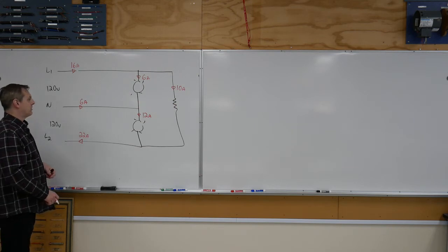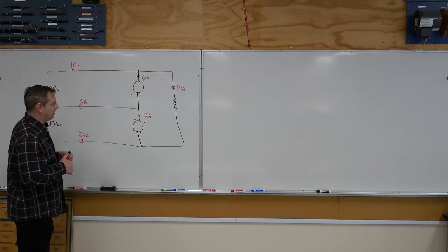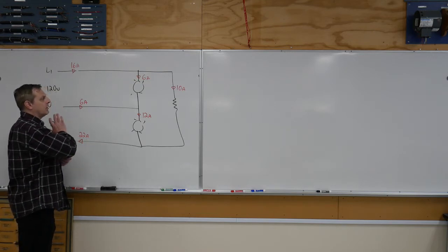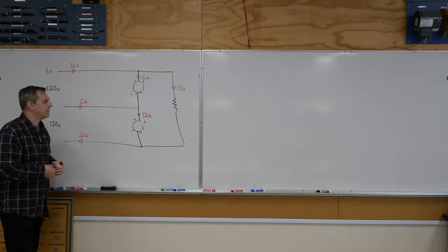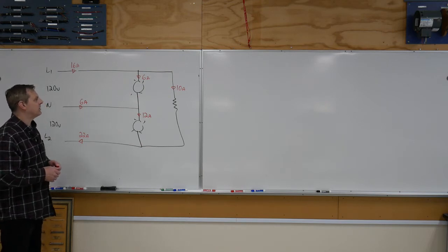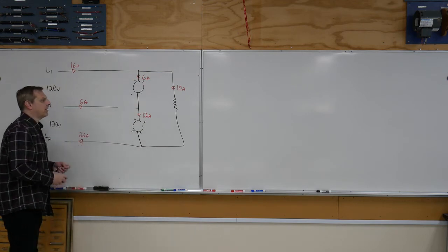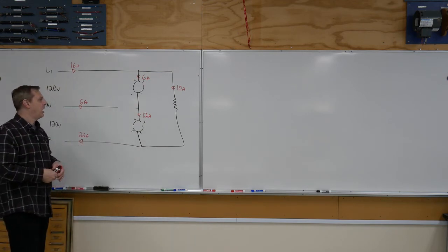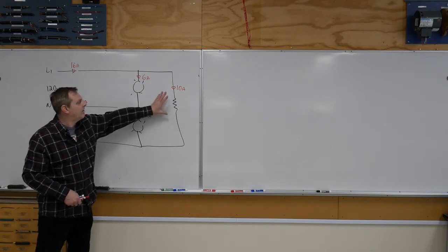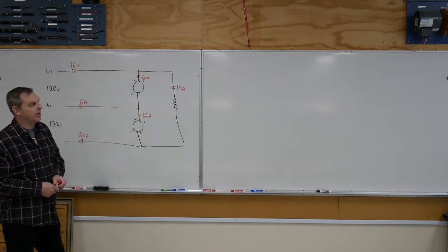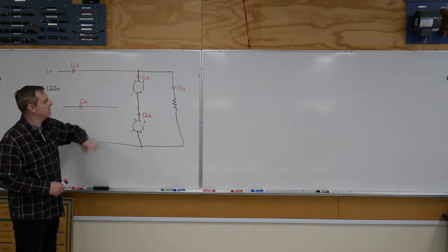So in this circumstance, with the unbalanced neutral, if all our connections were good, this is the worst case scenario, or I guess the best case scenario you could say. However, if we made a mistake and did a bad splice in here, we need to analyze what effect that would have on this circuit. Keep in mind, that misconnection does not have any effect on what's going on out here at my 10 amp load. That 240 volt load is unaffected by this. We're only going to deal with what's happening inside here.